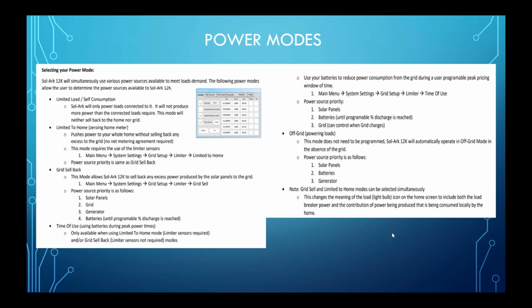This is a very big, important one, and you can use it in conjunction with Grid Sell. For instance, if you wanted to offset the loads with solar and only use the batteries to offset your main service panel loads and not sell back, then you can use a conjunction of Limited Power to Home and Grid Sell with what we call time of use, and I'll break that down in a little bit. That allows the customer to really take advantage of their full solar throughout the entire day, and then also use the batteries at night to really take advantage of the savings without pulling power from the grid.